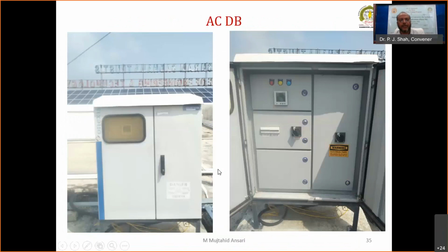Now this is the ACDB. I have already told that the ACDB should be installed on the rooftop area only, because it becomes easy for maintenance and testing purposes. It is the outdoor type, so definitely it should have a canopy. It is weatherproof, IP65, and inside there is a second double door. This is the first door and this is the second door, and there are 3 inverters: a 30 kilowatt inverter, a 20 kilowatt inverter, and a 50 kilowatt inverter. They are connected to a single switch, a 200 ampere MCCB, which is connected with the AC supply.